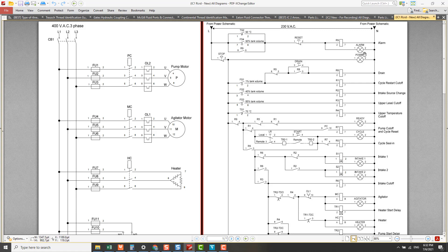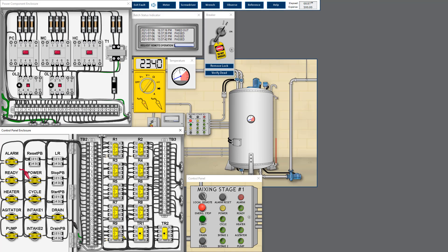I'll still check the earth fault at the load for this parallel circuit. I normalize back the connection, then open R9 and Alarm. The resistance remains the same, meaning there is no earth fault before the load and at the load.